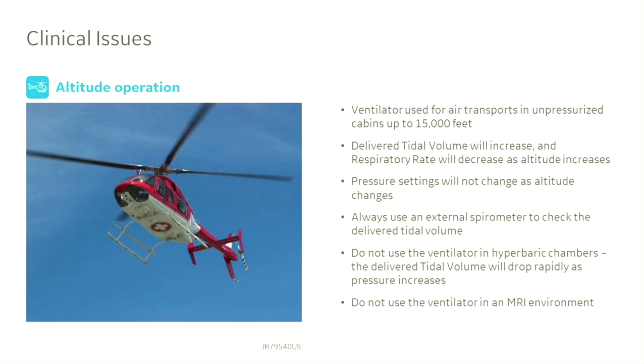Air transport and high-altitude operations. For air transport and high-altitude operations, the Newton A-E's delivered tidal volume will increase and respiratory rate will decrease as altitude increases. For this reason, the use of an external spirometer is recommended. Pressure settings will not change as altitude changes and is approved for altitudes up to 15,000 feet. Do not use the ventilator in hyperbaric chambers as the delivered tidal volume will drop rapidly as pressure increases and it is not indicated in that setting. The Newton A-E is not approved for MRI use.